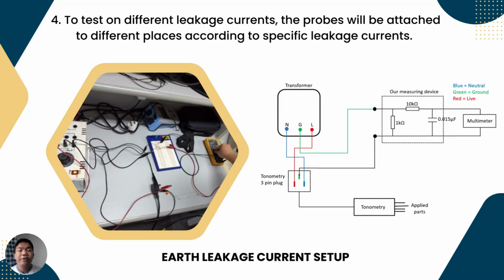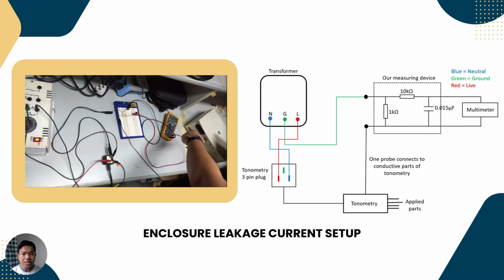To test the different leakage currents, the probe will be attached to different places according to the specific leakage current. This one is the earth leakage current setup. Both transformer's live and neutral wires are linked to the tonometry's live and neutral terminals respectively. The tonometry and the ground terminal of the transformer were both attached to the measuring device. For the enclosure leakage current setup, this is the same as before, except one probe connects to the conductive parts of the tonometry, which is the chassis.